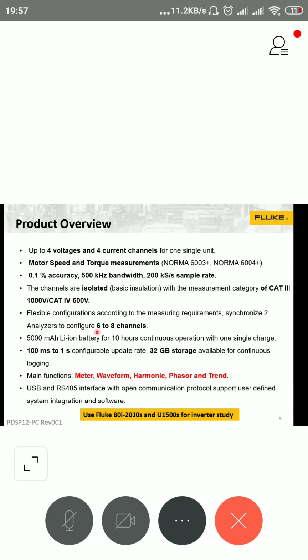And synchronizing between two equipments is possible. If you have purchased equipment with 4 voltage and 4 current channels, and you come across an application where you want to measure 3-phase input and 3-phase output, so you need a 6 or 8 channel. Synchronizing between two equipments is also possible. And when I told you that you can carry this equipment to the field, it means that it comes with a battery. This battery can give a battery backup of up to 10 hours in the field.